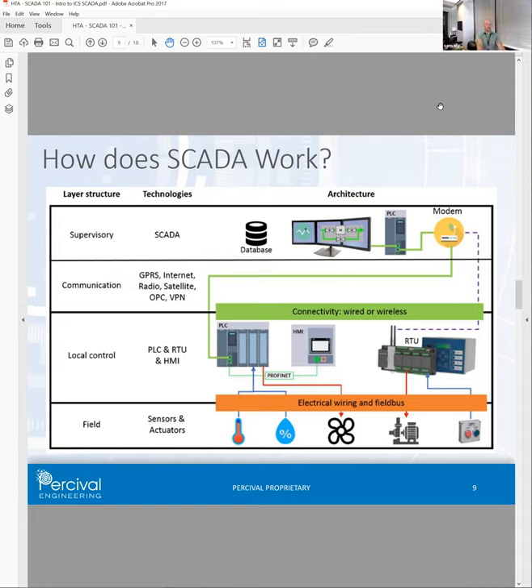So all of those controls now connect up to this RTU. The RTU then pushes it over to a PLC. The RTU's job is to talk to a whole bunch of different devices - basically you'd put one in a room full of equipment. Instead of wiring every single piece of equipment all the way back to the PLC, you'd wire them all up to that RTU, and the RTU acts as a data concentrator, if you will. So everything reports to the RTU, then the RTU reports up to, in their case, a local server. That local server was adjusting this - it would figure out all the readings and values. That would go over Wi-Fi to his iPad, where the guy was clicking the button saying pump from this tank to the next. Any questions on this sort of hierarchy?